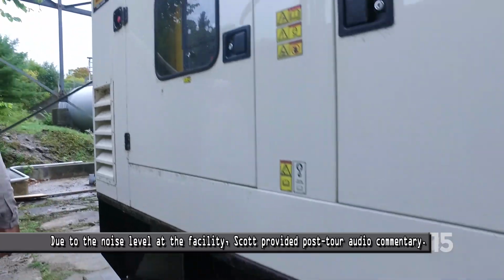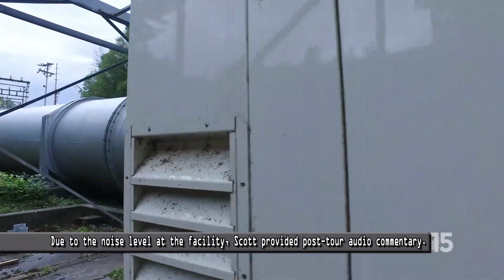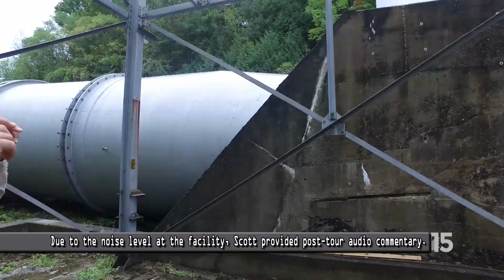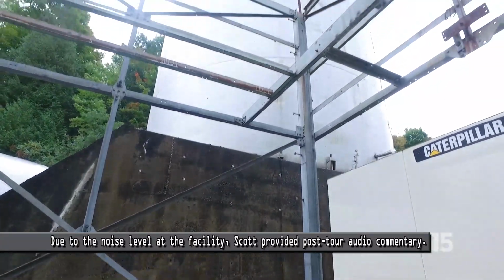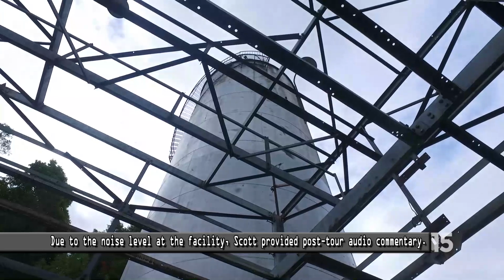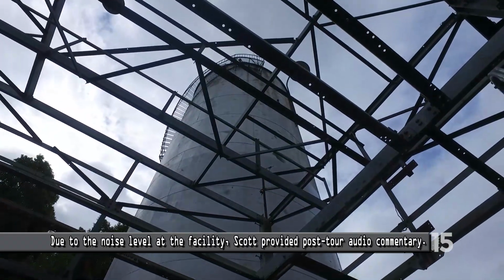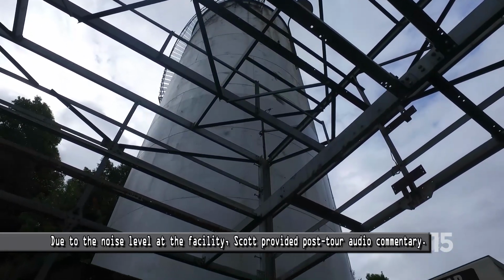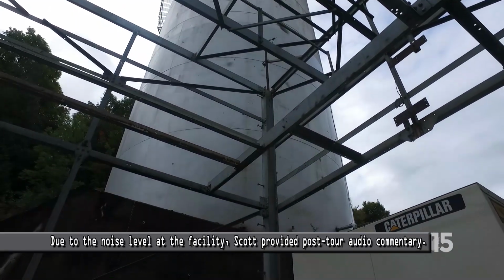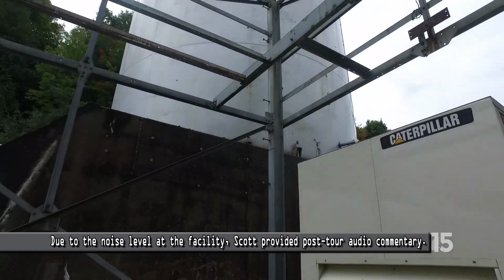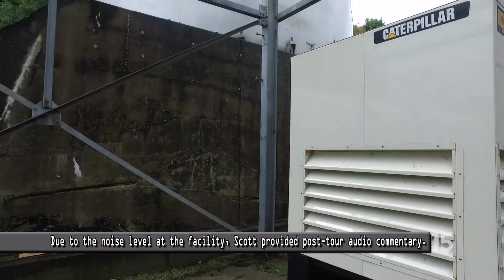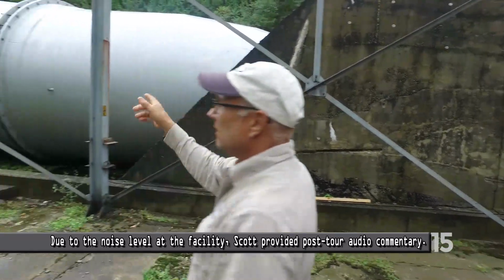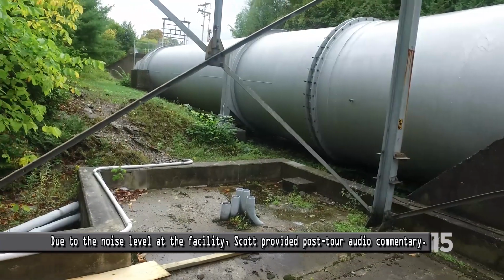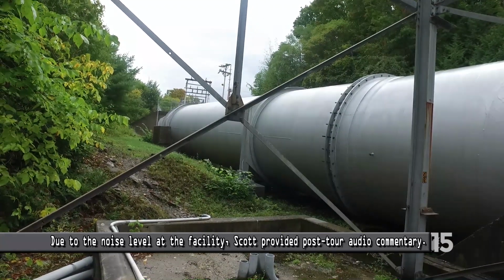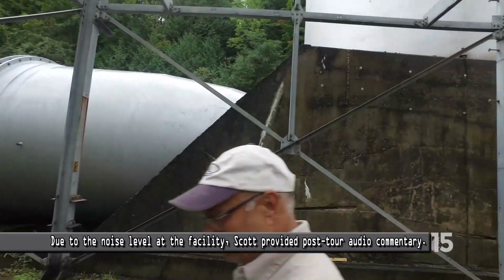And we also have a surge tank. In the case of the plant tripping offline, the momentum of the water coming down the penstock needs to go somewhere, and that's what the surge tank is for. It protects the equipment from hydraulic damage. This is our penstock, bringing water down from the pond down into the manifold to divert water to each of the 4 units.